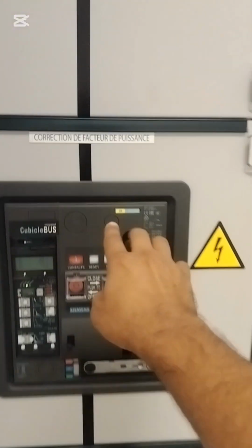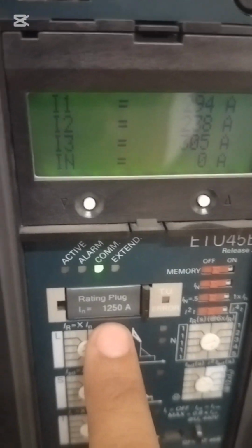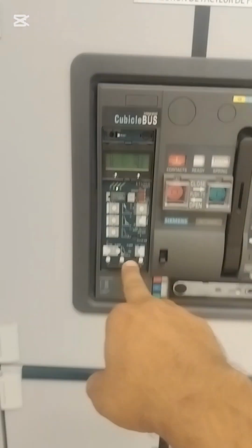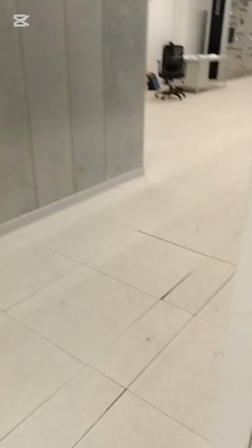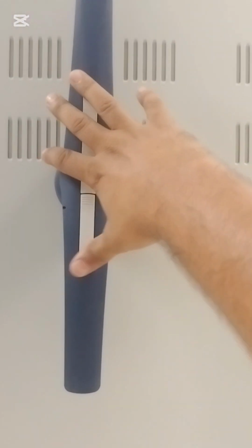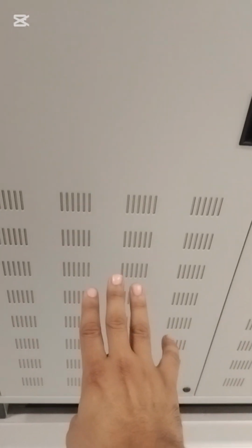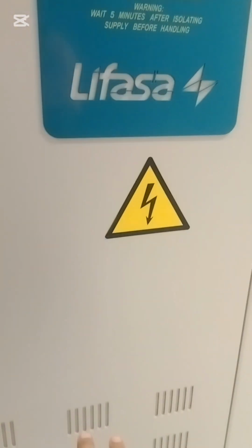I will show you this panel. This is coming from this bus bar. How much capacity does this breaker have? You see 1250 amps. I will show you where this breaker output will go. The output goes in this place, going inside. This is the back side; I will show you after that how we can connect. One breaker is there, an isolator. This is the isolator. Here is the breaker inside. You see this one, a main contactor, it goes there. After distributing there, the downside has a capacitor bank. So here I can show you.